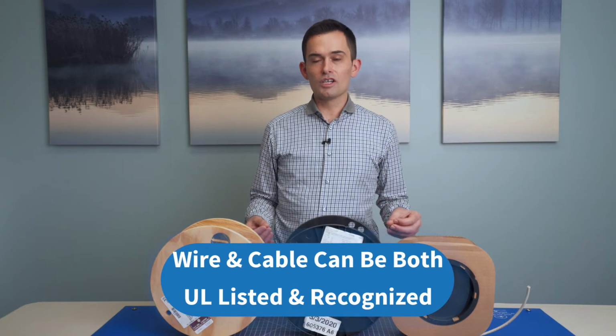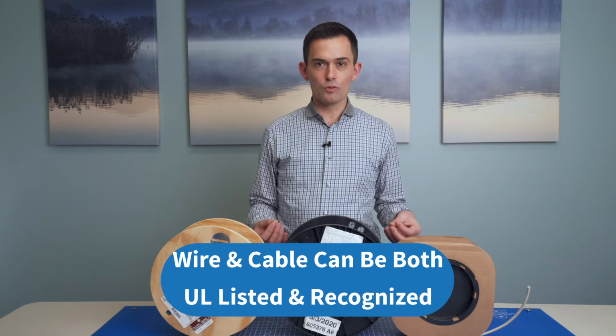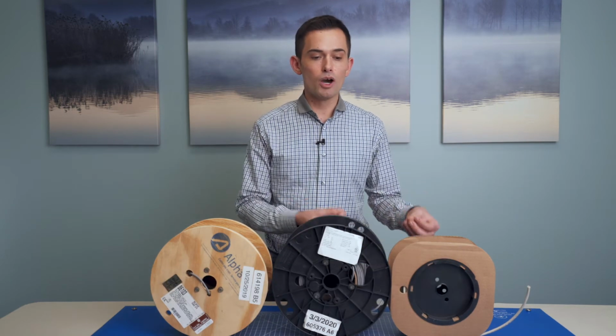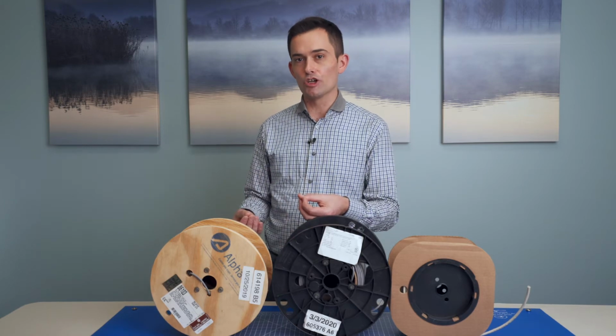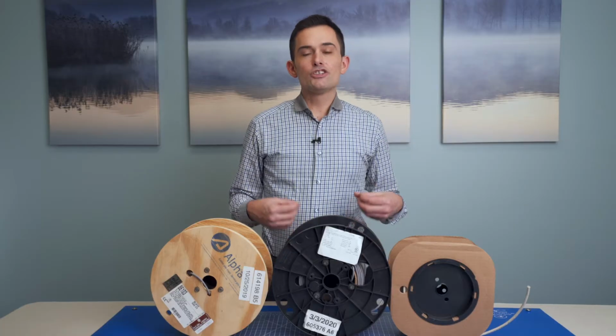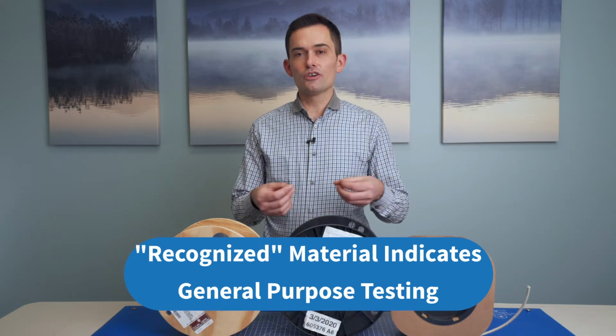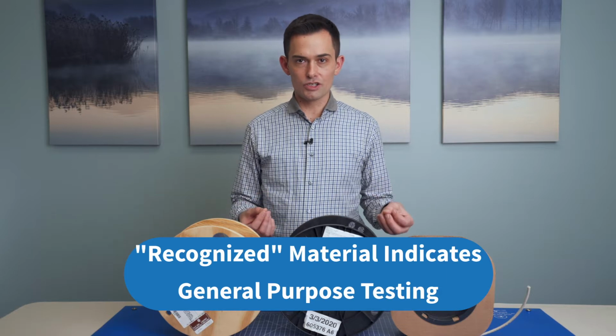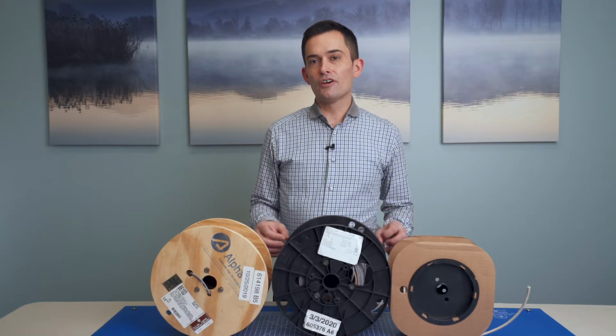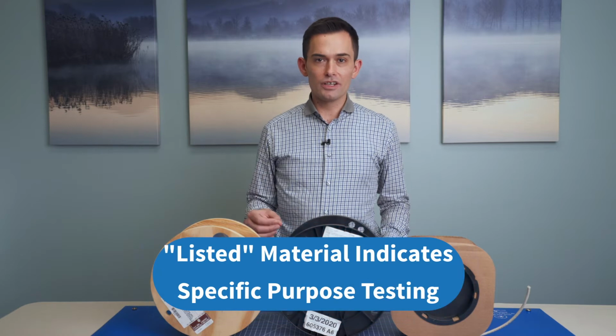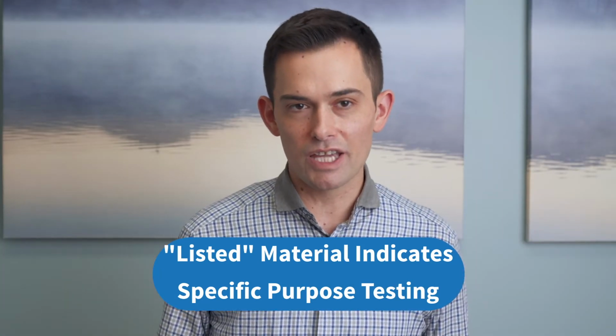Both of these terms can also be used to apply to raw wire and cable, which at first seems to not make very much sense because you would think of wire and cable as being a component, something part of something larger. Material that bears a UL recognized mark may just be tested for a certain general set of environmental conditions. It indicates that the material has been tested for general purpose safety.